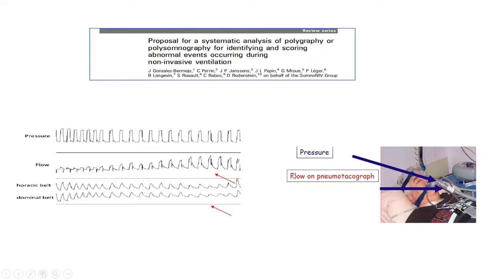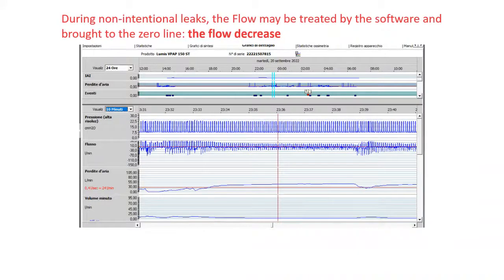This view is from an external pneumotach close to the interface. What we see in software is treated data — all software treat data coming from the flow sensor. You have to know how to use the information coming from the software. For example, the majority of software bring the flow close to the zero line every time flow increases due to leaks.